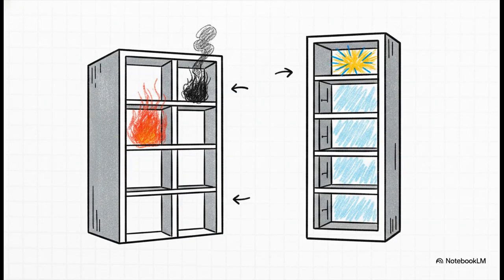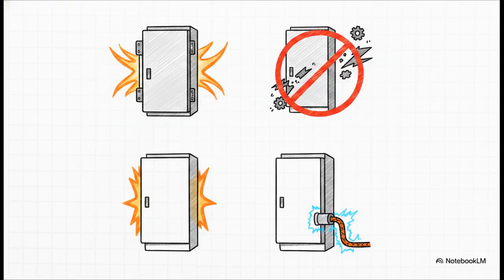So to understand how we actually survive that, let's quickly look back at the foundational architecture of the switchboard. Just as a recap, we know these boards feature a metal-clad construction broken down into 5 distinct internal compartments: the bus bar, the breaker, the cable terminal, the secondary equipment, and the operating unit. It's kind of like a high-rise apartment building. If one unit catches fire, thick concrete walls guarantee it cannot spread to the neighbor's unit. That is exactly what this metal-clad construction is doing with rigid steel partitions. It isolates these explosions to a single sealed unit: one fault, one compartment, never the whole board. And this setup perfectly illustrates what arc-proof compliance actually means when a fault detonates mid-service.